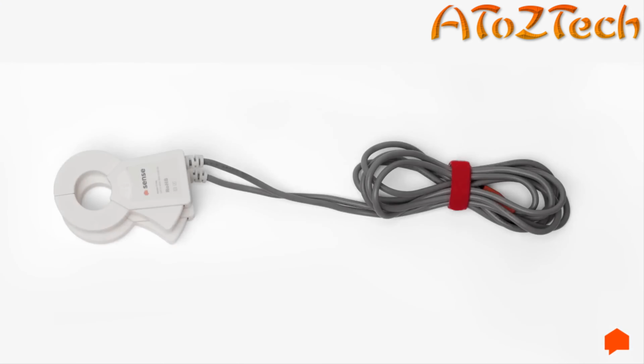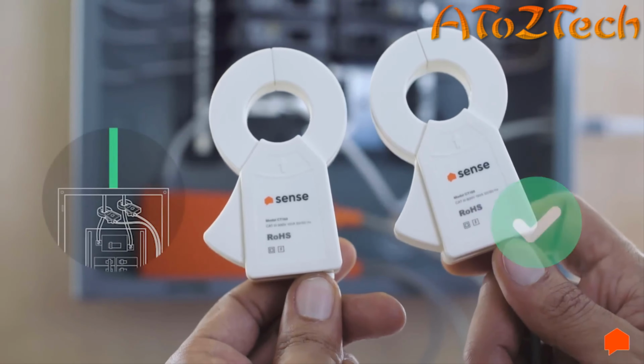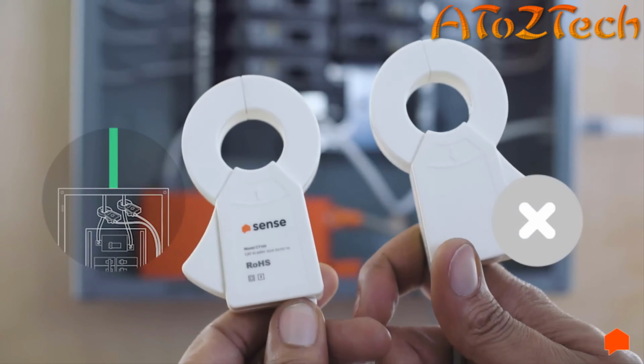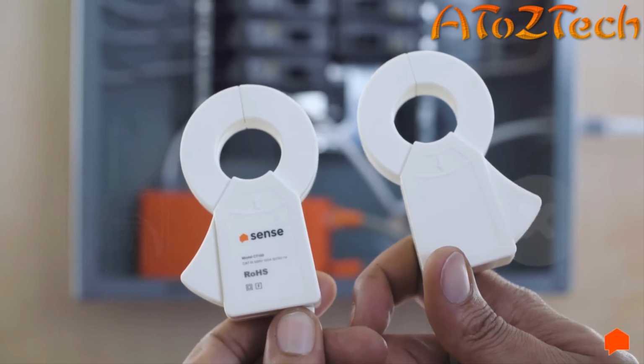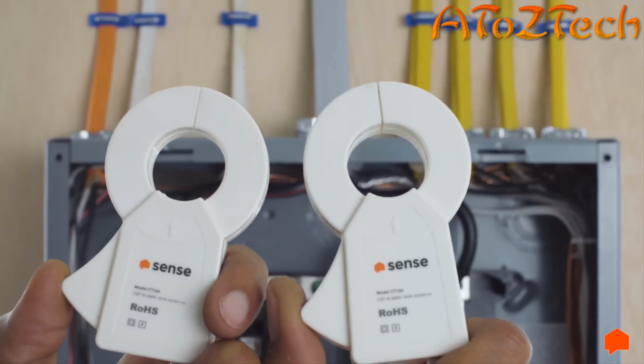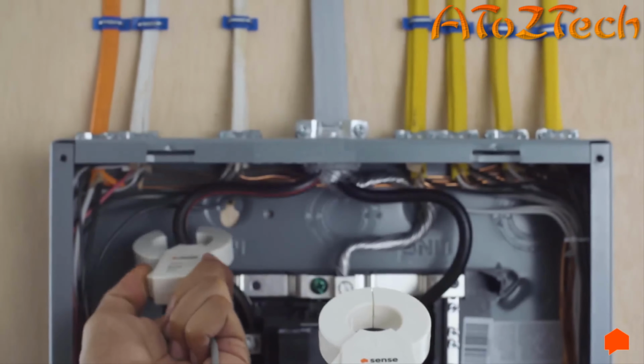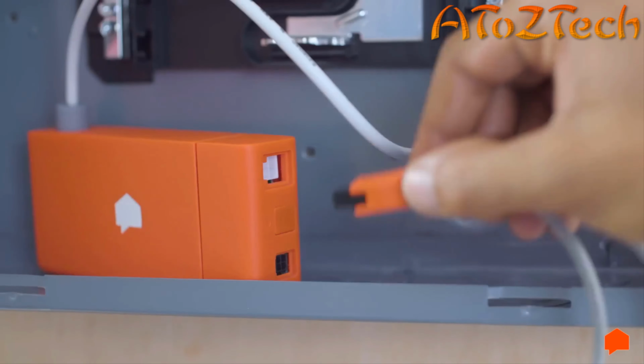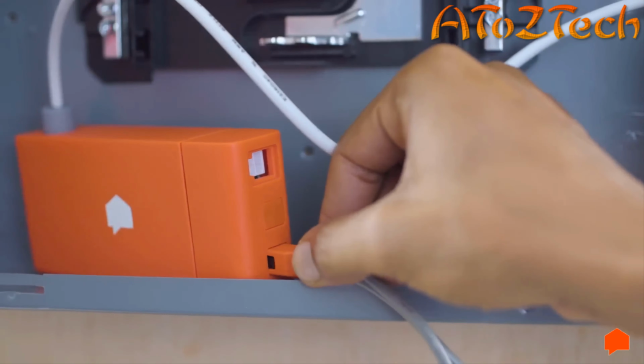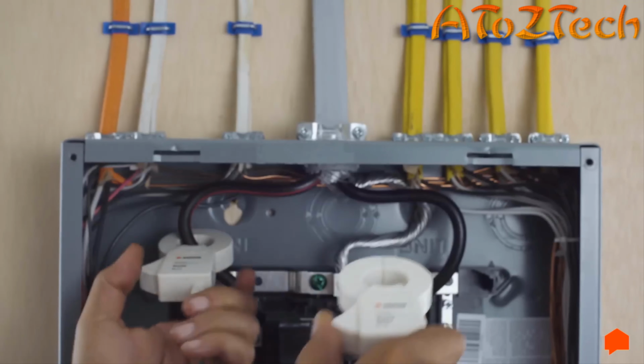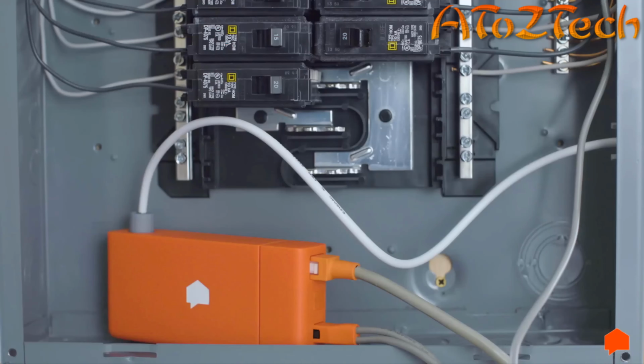On to the sensors. Make sure that the labels on the 2 current sensors are both facing the power source. If your service mains have loops, follow the loops to make sure they're facing the same direction. Clamp the current sensors around the 2 main service breakers. For safety reasons, it's important that you first plug the sensor cables into the monitor and then attach them around the mains. Sense can now measure the current running through your home.